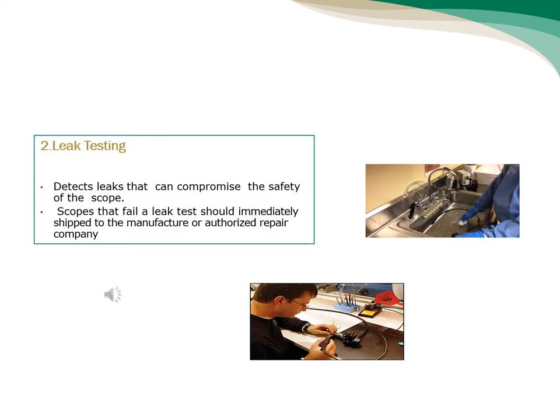Leak test: it is performed to verify the safety and integrity of the scope. If any problem is identified with the endoscope, it should be repaired correctly by a qualified specialist.